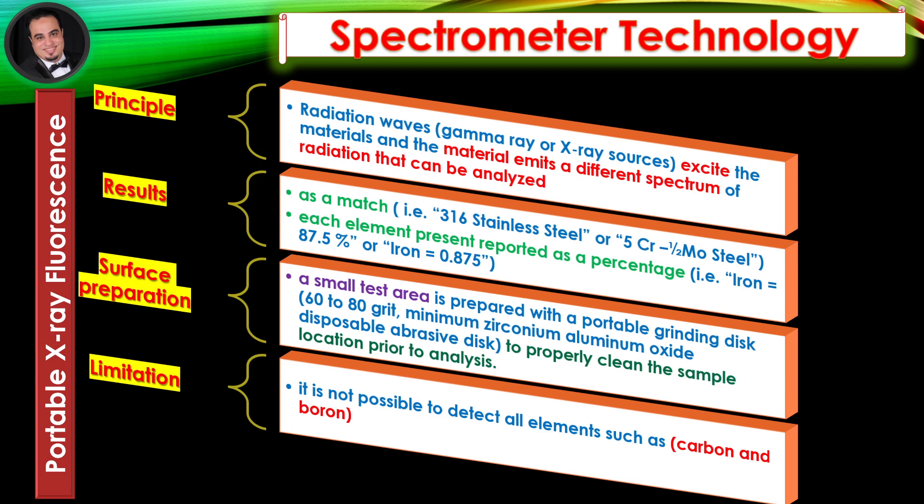Surface Preparation: A small test area is prepared with a portable grinding disk, 60 to 80 grit, minimum zirconium-aluminum oxide disposable abrasive disk, to properly clean the sample location prior to analysis.